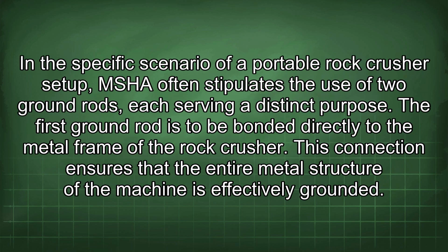In the specific scenario of a portable rock crusher setup, MSHA often stipulates the use of two ground rods, each serving a distinct purpose. The first ground rod is to be bonded directly to the metal frame of the rock crusher. This connection ensures that the entire metal structure of the machine is effectively grounded.